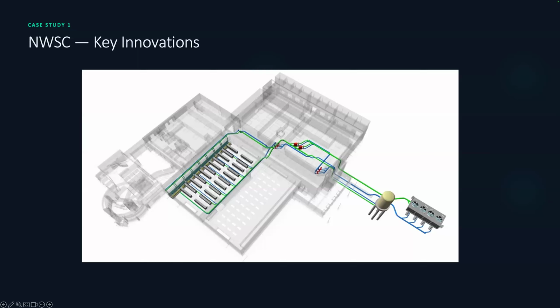The condenser side is the same, and we were very concerned at NCAR about thermal ride through, especially as you got to these really high densities. And systems will shut down in like sub-second, 2 seconds when they're overheating. So that large storage tank is just a thermal battery. We dump the heat to that location, and then we pick it up from the towers, and it creates this buffer, which gave us something more like 35, 40 minutes to react instead of seconds. That was 165,000 gallons of water in an insulated tank.